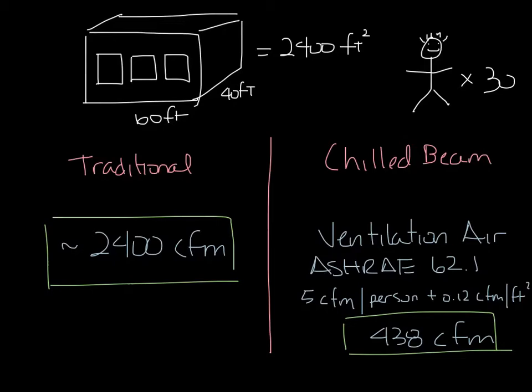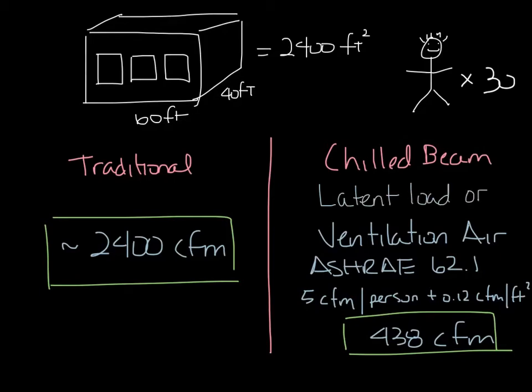Now in reality, you're probably not going to use 438 CFM because you have to handle the latent load as well. So what you would actually use is the higher CFM requirement between the latent load and the ASHRAE 62.1 ventilation requirement.